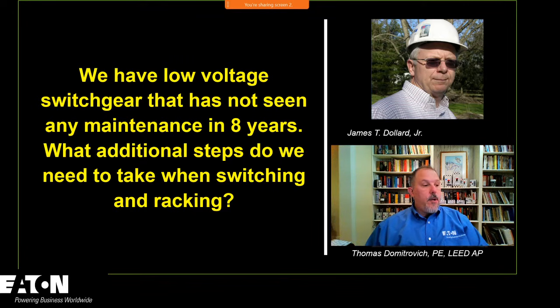Yeah, sure. So if you think about one of the most hazardous areas in a power distribution system, it's the service entrance equipment, and I would also say that first panel board on the secondary of really any transformer. Because to your point earlier, the clearing time is based upon the upstream overcurrent protective device. And so I think we had a perfect storm going on from a National Electrical Code perspective. You had changes for the line side barriers in 408 in the 2017 code, but they had to put an exception in for when you had a panel board that was leveraging the 6 disconnects inside of an enclosure. And because you can't barrier the whole bus, because when you take that dead front off of that enclosure, you're staring at either a copper or aluminum bus and 6 disconnects. If you just picture a panel board in your head.